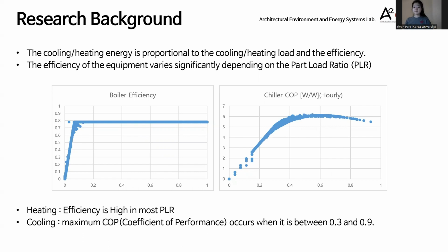On the other hand, equipment efficiency depends on the part load ratio (PLR), which represents the ratio of the actual load to the equipment's capacity. For boilers used in heating, they operate at high efficiency except at very low PLR. However, for chillers used in cooling, the variation in coefficient of performance (COP) based on PLR is significant. At low PLR, the chiller operates with very low COP, resulting in high energy consumption even with a lower cooling load.